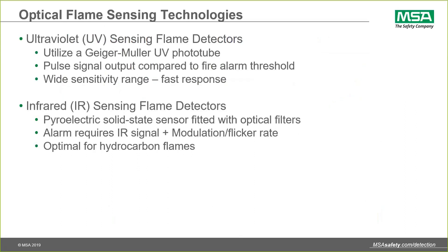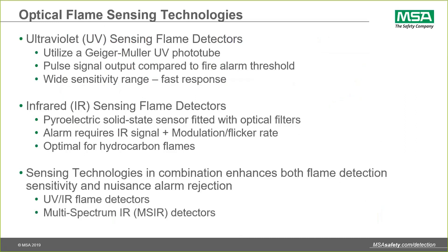Infrared sensors are usually a pyroelectric crystal solid-state sensor fitted with an optical filter to allow it to measure specific frequencies of light. As you can guess, 4.3 microns is one of those key frequencies. Additional signal processing requires not just that energy level in the infrared, but also a modulation or flicker rate, because hydrocarbon fires breathe — they have a flicker — and that's part of the signal processing requirements. They are optimal for hydrocarbon fire detection.